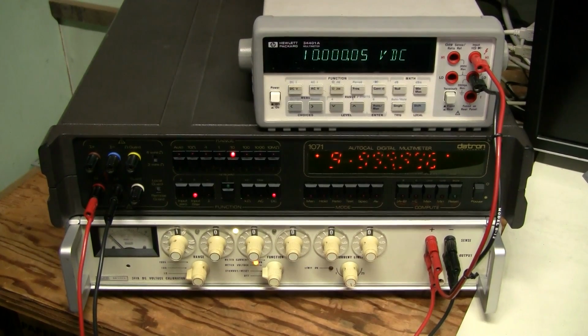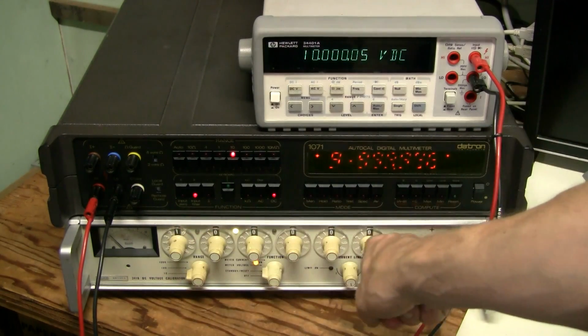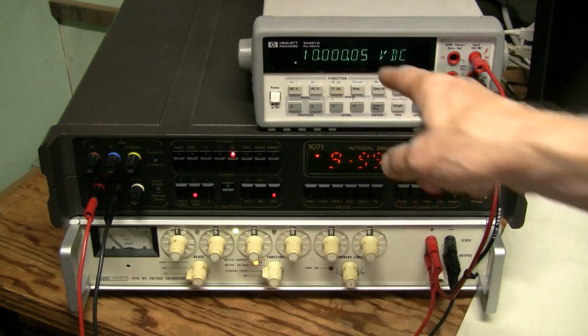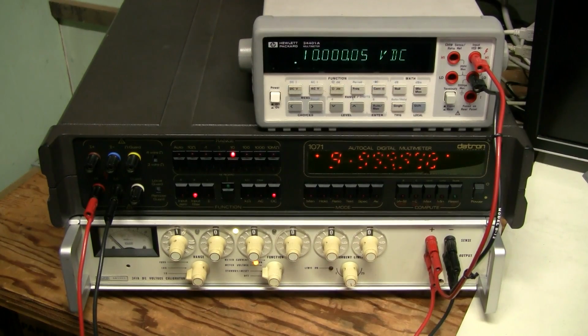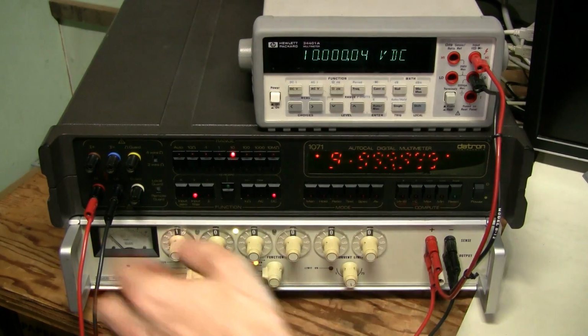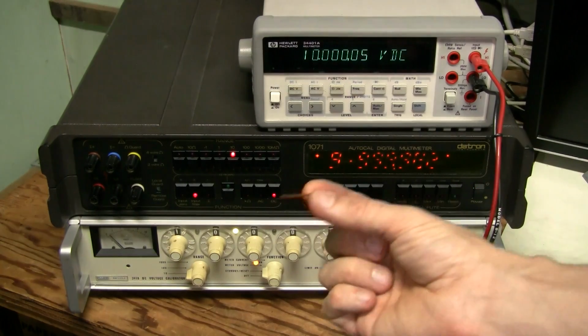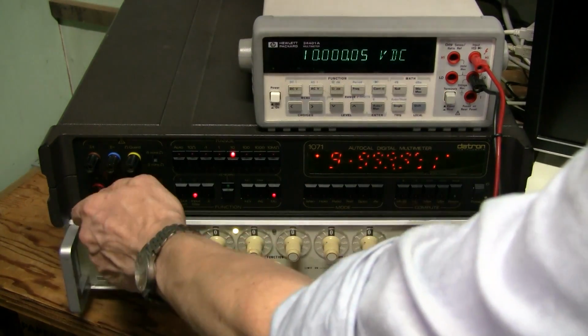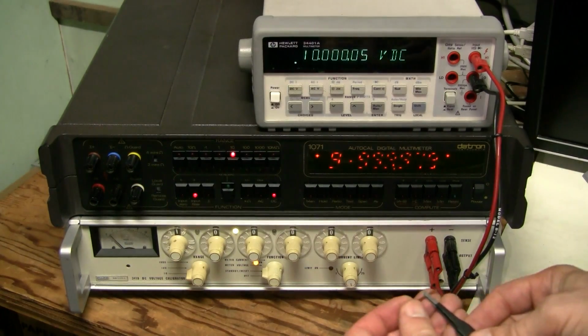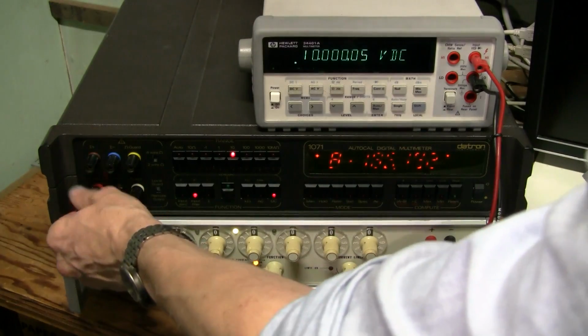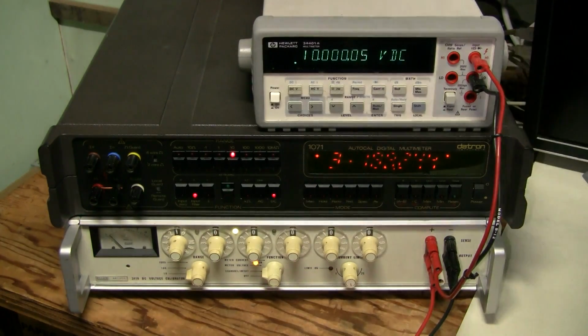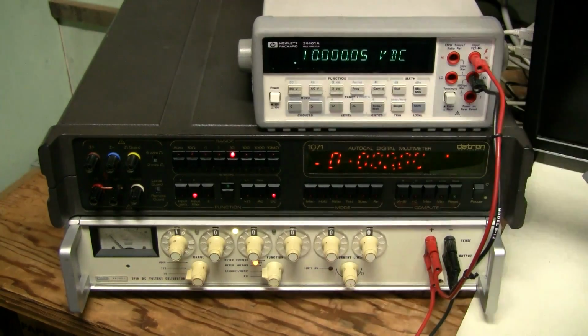Here it is, my trusty Hewlett-Packard 34401A meter, and as you can see, according to this meter, the 10 volt setting on fluke is about 4 to 5 ppm out. So let's set a 10 volt range on Datron according to this meter. First let's do the 0, which is done by applying a short piece of copper across input terminals. And let me turn that key on the back to calibration. As you can see, the 7th digit disappeared.